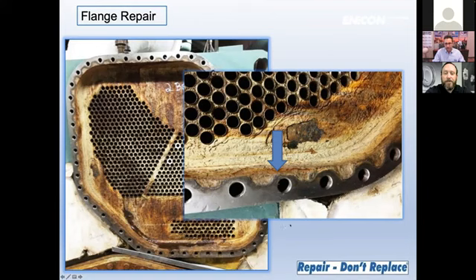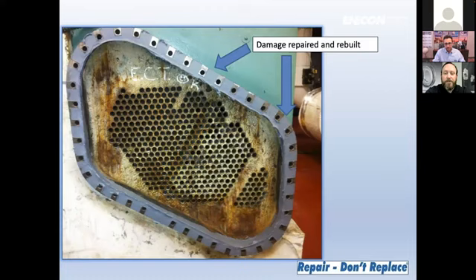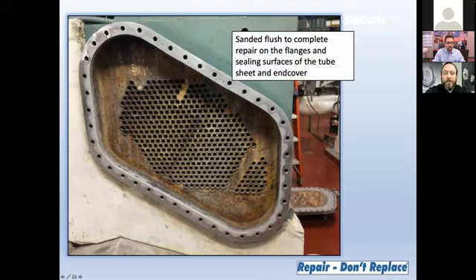This type of repair is typically completed in one day and put back in service the following day. The first thing we do to complete this application is complete surface prep on the areas, creating a clean, dry, rough surface to both the tube sheet and end covers that are going to be rebuilt. After the surface prep is complete, ENECON's Duralloy material is applied to the surfaces, typically overbuilding the damaged flange areas in order to rebuild the flanges back to specification. Once the Duralloy has cured, we sand the Duralloy back down, making sure that it's flush all the way around the flanges on the tube sheets and end covers. And the next day, it's put back in service.